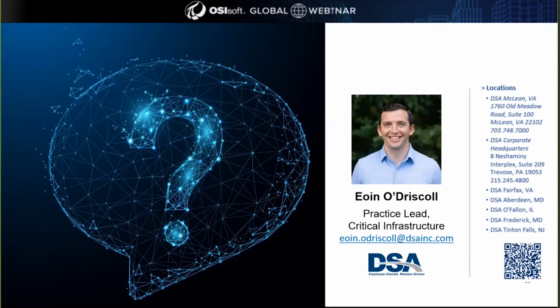That's a good question. There are a couple of different ways to get data securely from automation systems installed locally behind firewalls to the cloud, if that's what you desire - it doesn't have to be deployed that way. One is, I'd say, the standard with firewall exceptions, which is an industry standard. But there's also a more secure way, through data diodes. A data diode, or unidirectional gateway, is a physical device built so that it only has circuitry to allow data flow from the local asset to the enterprise level, making it physically impossible for data to flow the opposite direction. That's the second option, and it definitely locks down those local networks.